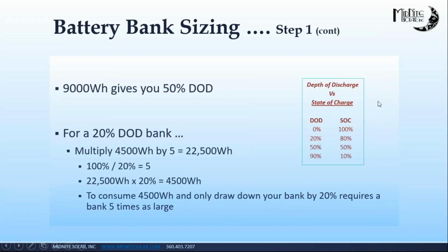So depth of discharge versus state of charge, the inverse concepts. If I draw down my battery bank 20%, I have 80% left over. That's the way to look at it. So 50% is 50. If I draw it down 90%, I'm abusing the batteries. I'm going below that 50% that I just talked about, and I only have 10% left over. So state of charge would be a percentage indicator you would see on your charge controller. Like the classic, we have that. We use our little current sensing device called the Whizbang Junior, and it gives us a state of charge percentage. The state of charge you could think about as being like the gas gauge on your vehicle. If your gas gauge says 75%, you got 3/4 of a tank of gas. So that is the analogy on that.